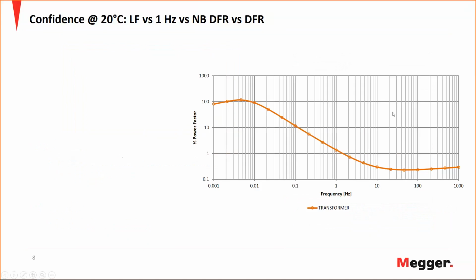And what this all drives down to is that you have different confidence levels, different feelings about your asset and its reliability based on which testing you perform. If you do line frequency, that is good. You get good confidence because at least you have some information about your standard. About your asset, and you can evaluate those based on the standard. And this is typically the required 10 kV test that you do.